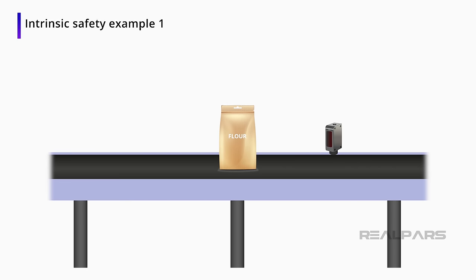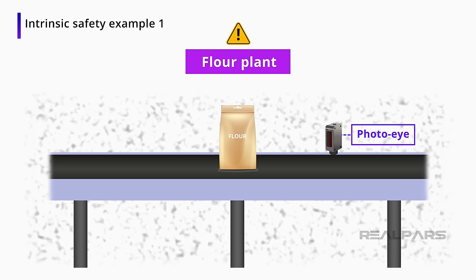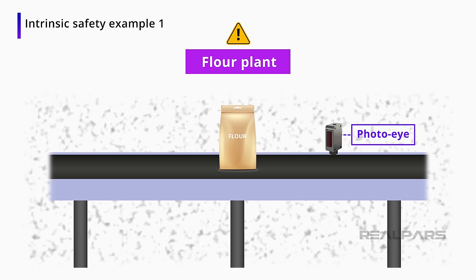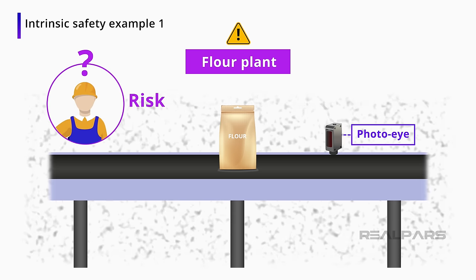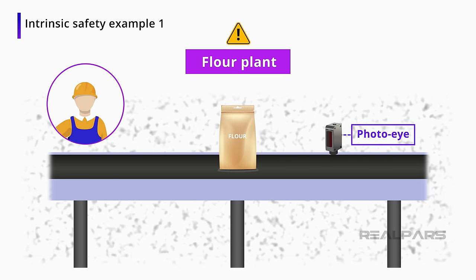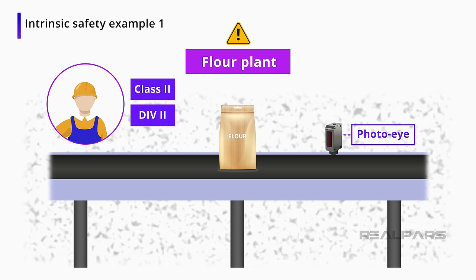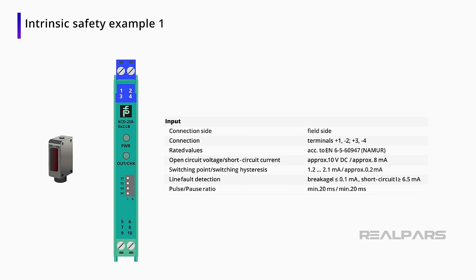Here is an example of intrinsic safety in an automation environment. You have a photo eye on a conveyor in a flour plant. Due to the dust ignition hazard, you are tasked with specifying a solution to safely use the photo eye. Because of the environment, you will first look up the requirements for the room, then perform a risk assessment and decide that the room with the conveyor is Class 2, Division 2. Division 2 refers to the presence of a hazardous atmosphere under abnormal operating conditions. You then need to find an intrinsically safe barrier to place in the electrical panel you are designing, and find a photo eye that is compatible with that barrier.